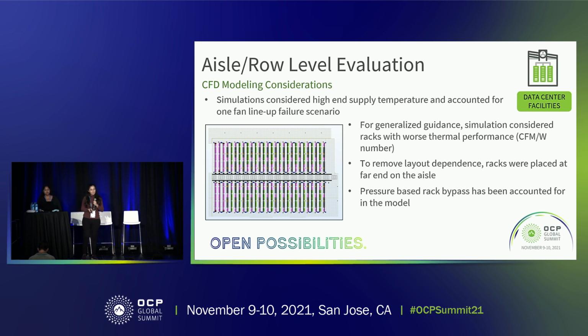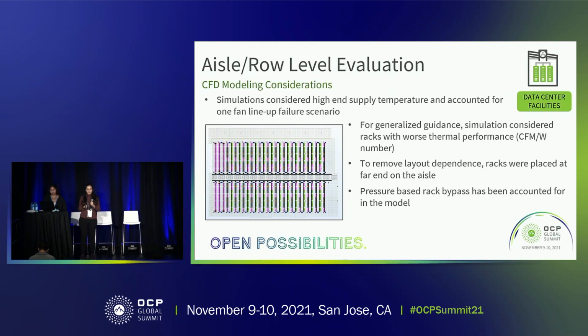So when setting up these DC-CFD simulations, we try to simulate the worst case scenario so as to make sure that we will not run into any thermal runaway scenarios or any thermal risks while in operation. The simulations considered the high end of the supply temperature that we have in our data halls. And we also try to take into consideration the scenario where we have one fan failure. Also, for generalized guidance, the simulations considered our hardware to operate at the higher end of its CFM per watt spec. And also, the hardware is deployed, as you can see here, at the very end of the aisles, away from where the cold air actually comes down, which again helps us simulate the worst case scenario that we might find in the data hall.